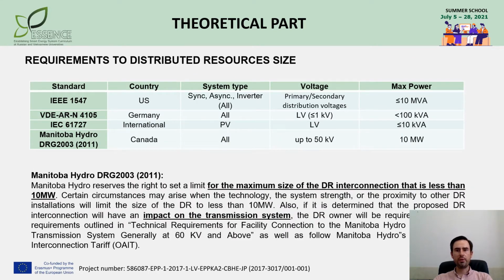The size of a microgrid isn't limited by its definition, but since it's a part of a distribution grid, its capacity is limited by the transfer capability of the lines and power transformers. Besides, the interconnection requirements in different countries clearly define a maximum size of distributed energy resources that can be connected to the utility grid. Since a microgrid is considered as one object representing a group of distributed resources, its maximum size can be from 10 kVA to 10 MVA. It is usually noted, as you may see from the example of connection requirements on the slide, that the size is limited by the capability of the distributed resource to impact the utility grid.